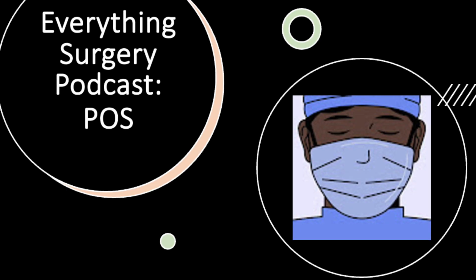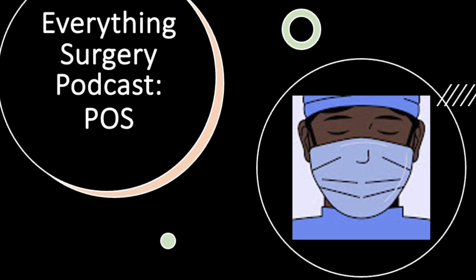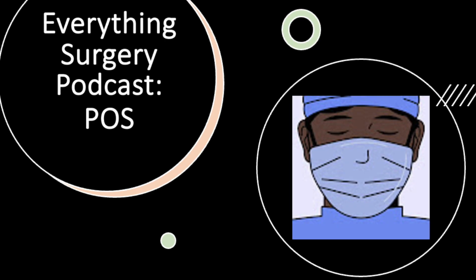The sterilization process. Step-by-step sterilization is not a single event, but rather a meticulous, multi-step journey. Let us walk through each stage. The process begins with what is known as point-of-use pre-cleaning, or pre-treatment. Here, instruments are wiped or rinsed immediately at the surgical field to prevent blood and debris from drying on them, which would make later cleaning much harder.